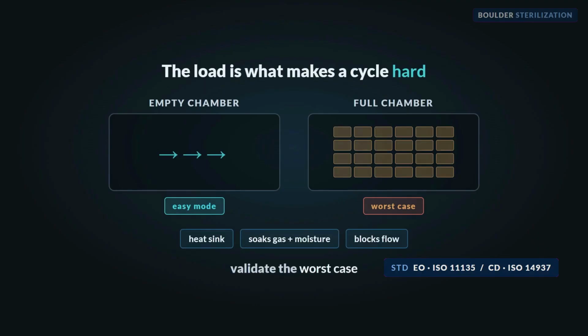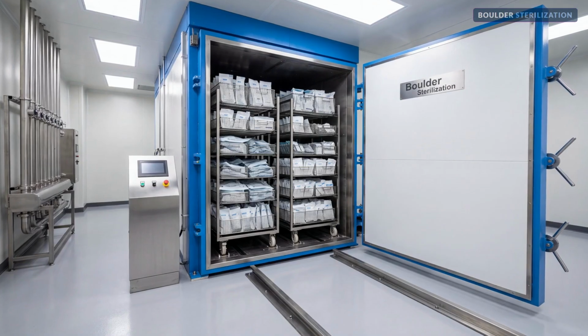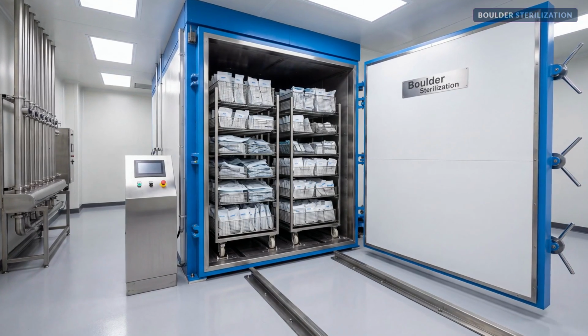A sterilization validation is specific to your product. We're proving the cycle sterilizes your device, and that includes testing the product itself. But a cycle is only as good as the toughest load configuration it has to get through. An empty chamber is the easy case. Gas flows everywhere, nothing gets in the way. A chamber packed for a real production run is the worst case.